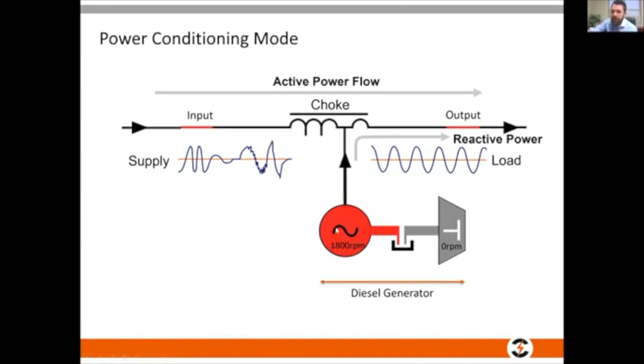If my input breaker opens or if the mains fails, I still have a problem. But within 5 seconds, my diesel engine will get to 1800 RPM. And remember, that's what we're doing for a diesel generator. My engine will get there within 5 seconds because unlike a diesel generator, I don't also have to pick up the speed of the alternator. Remember, the alternator was already spinning. But if this takes 5 seconds, I still have a problem because within 5 seconds of my input breaker opening and the engine getting to speed, this is going to slow down. And I just simply cannot allow this to slow down if I want to guarantee clean power, uninterruptible power on the consumer.